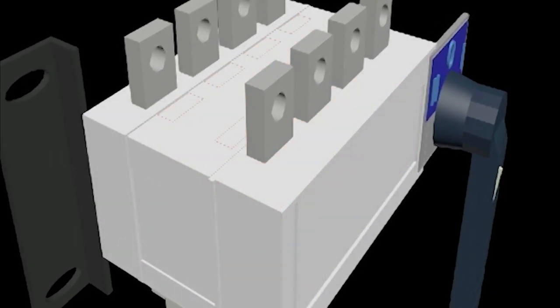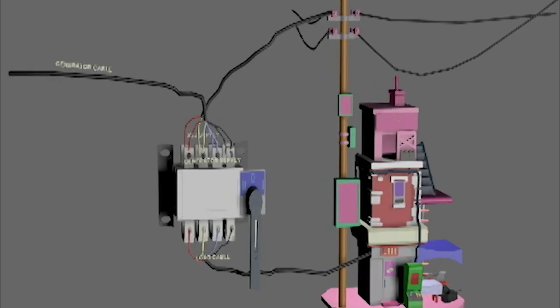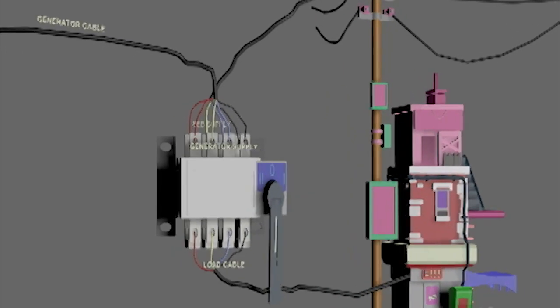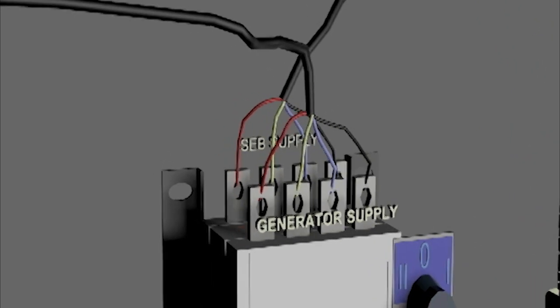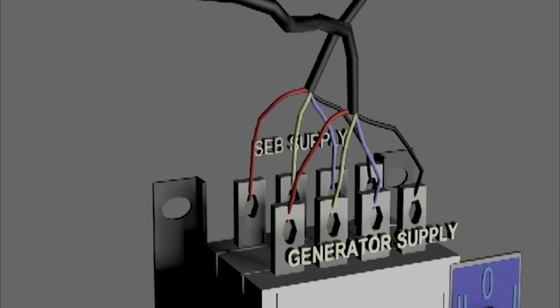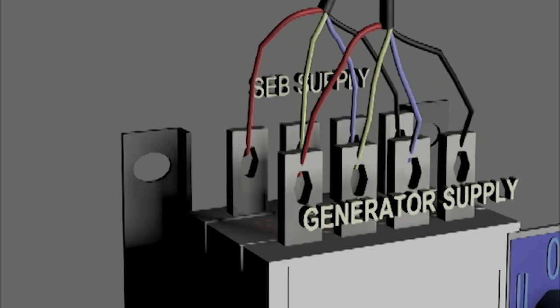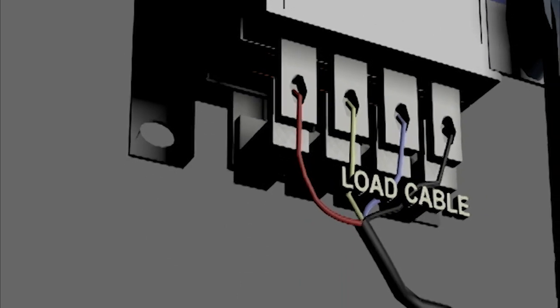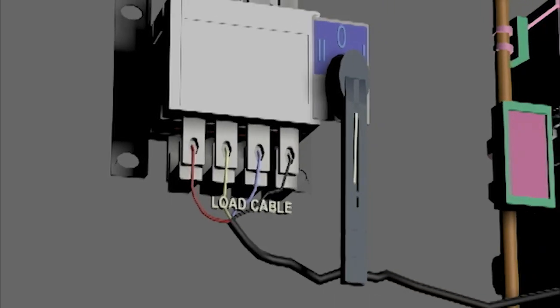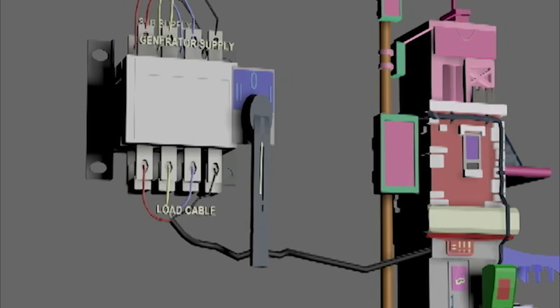Let us see how to use a changeover switch. In this setup we have a changeover switch where the upper side position 1 terminals are connected to the generator supply, and the position 2 terminals are connected to the state electricity supply. The lower set of terminals are connected to the load cable of a building.